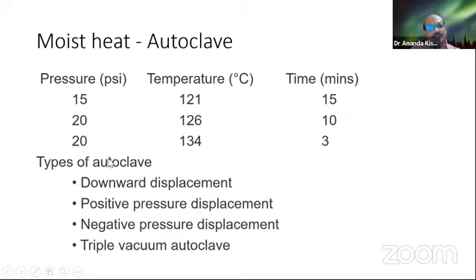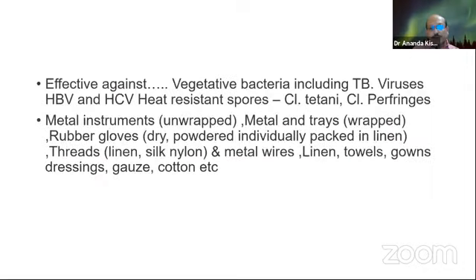There are several other procedures. This is the standard technique, but other techniques use 20 pressure, and 126 or 134 degree temperature, with the time reduced to as little as 3 minutes. But this is not standardized. Standardized is 15, 121, and 15 minutes. There are different types of autoclave, which is asked in the examination: the downward displacement autoclave, positive pressure, negative pressure, and the triple vacuum autoclave.